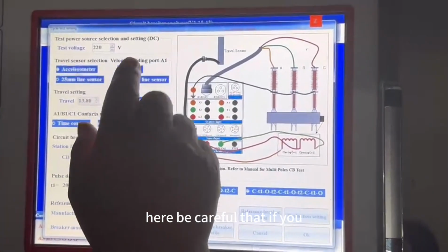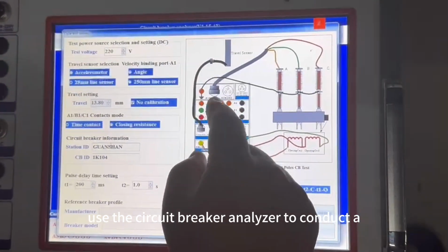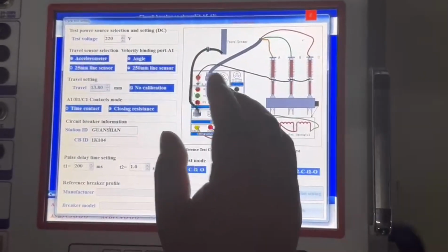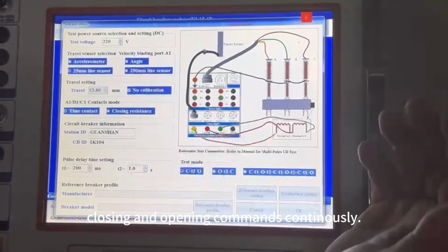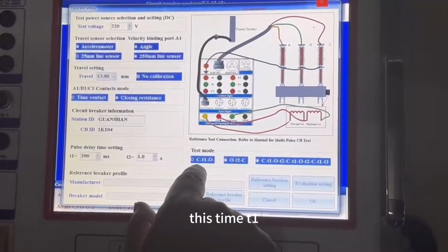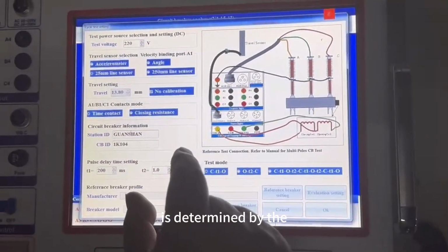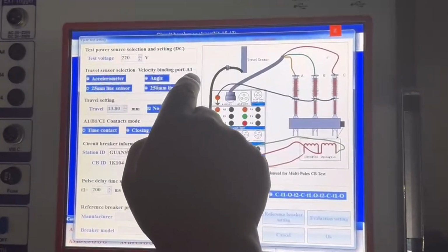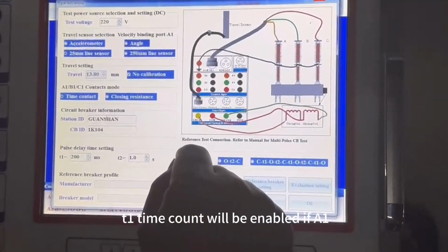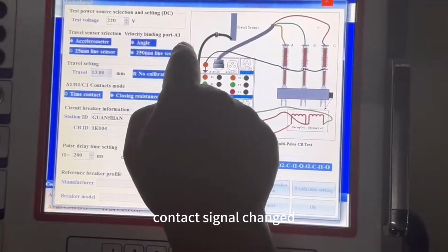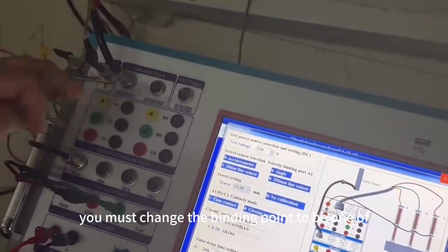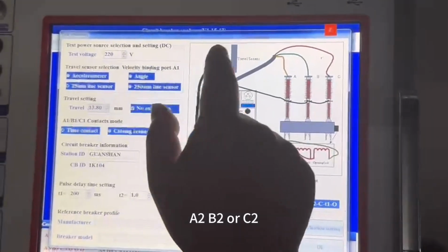Here, be careful that if you use the circuit breaker analyzer to conduct any circuit test, because the analyzer will generate closing and opening commands continuously, there is a time delay. For example, now we select CO, there is a time delay T1. This time T1 is determined by the contact signal of the bonding port. For example, now we have bonding A1, that means the T1 time count will be labeled if the A1 contact signal changes. So if you are using group 2, for example A2, B2, C2, you must change the bonding point to be one of A2, B2, or C2.